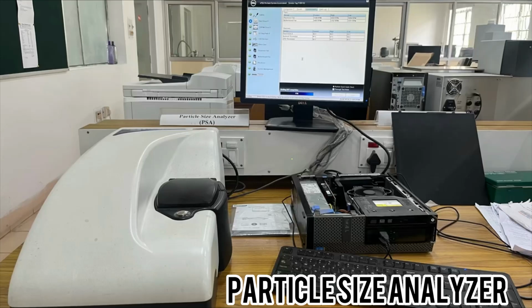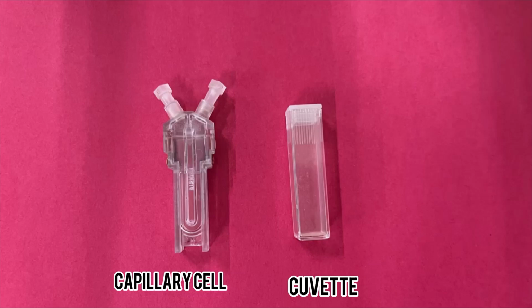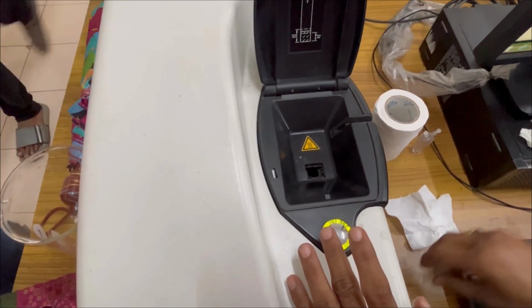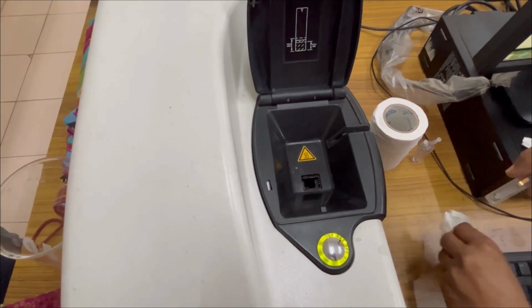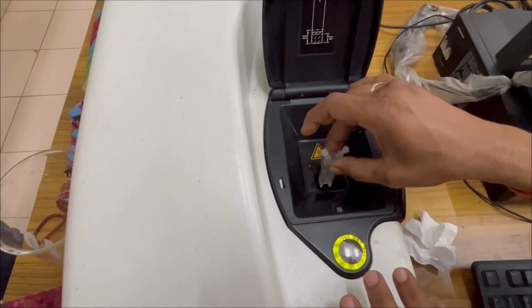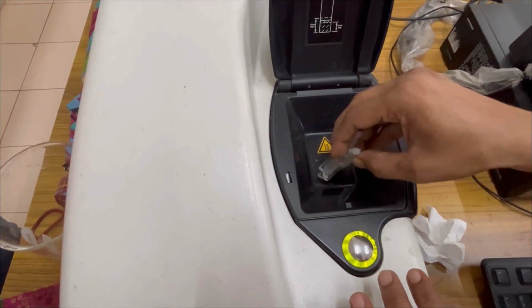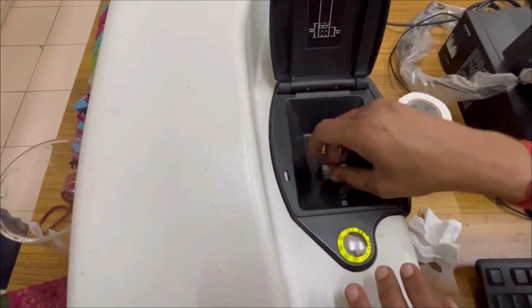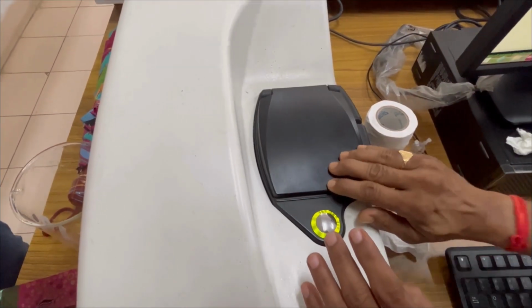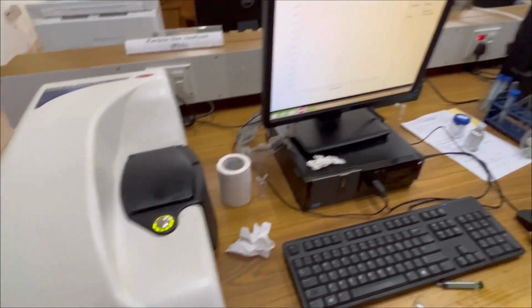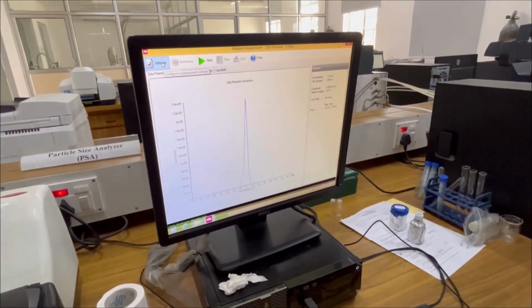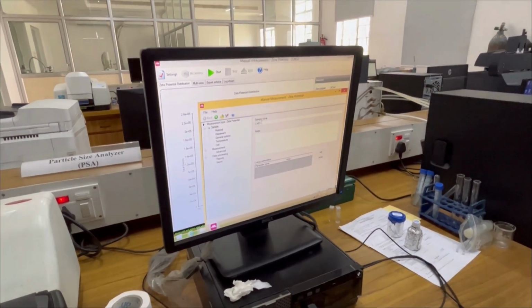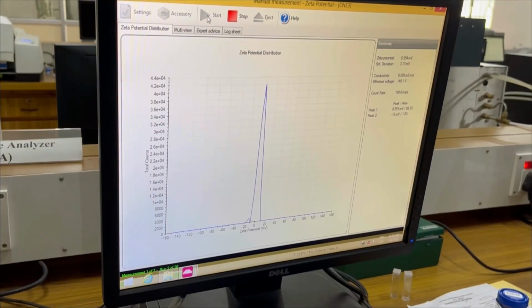This is the Zetasizer nanoparticle characterization system. This capillary and DLS cuvette are the major components of this instrument. This instrument is used to measure and analyze the size of particles in a colloidal solution on the basis of dynamic light scattering. The principle behind the zeta potential measurement involves the application of an electric field to the particle or molecule suspension and the subsequent observation of the movement of the particles under this field.